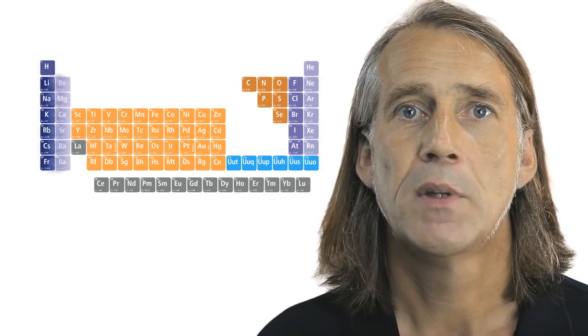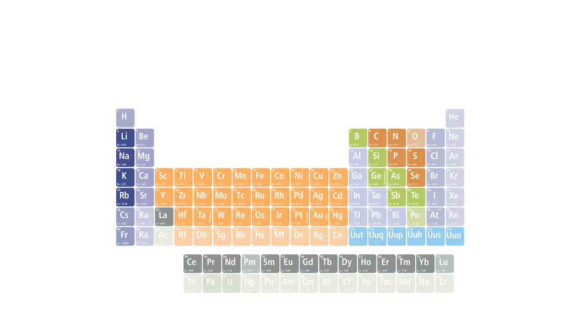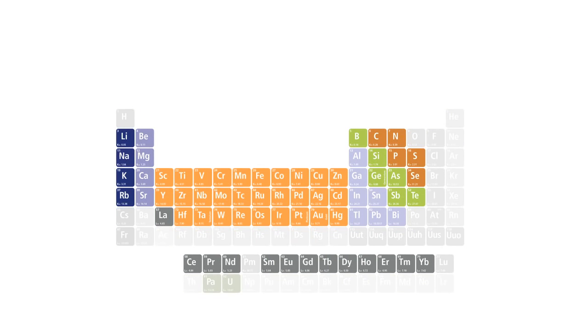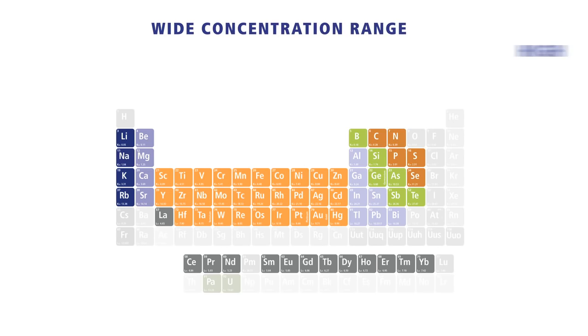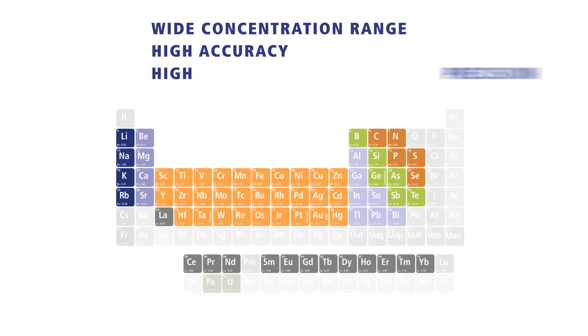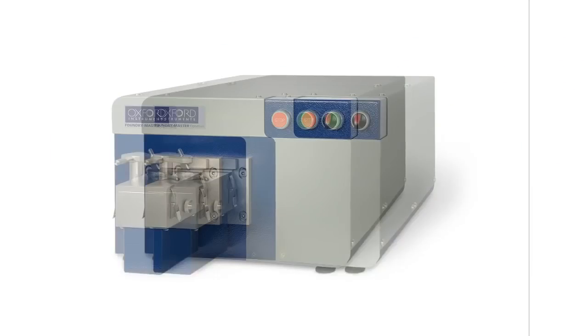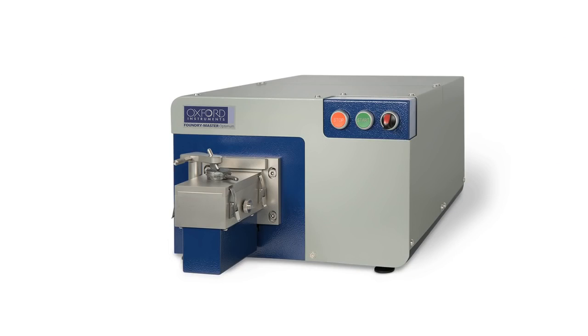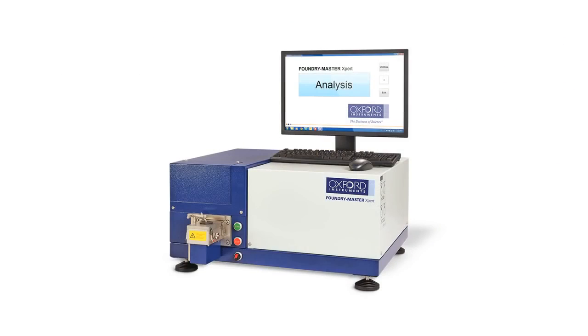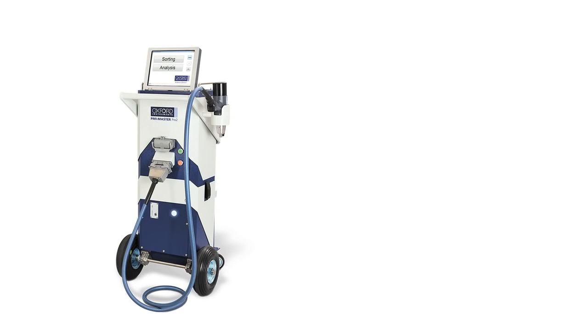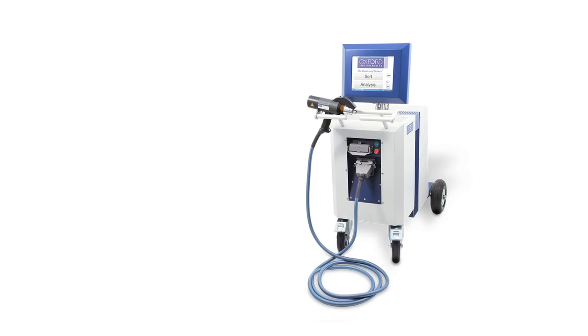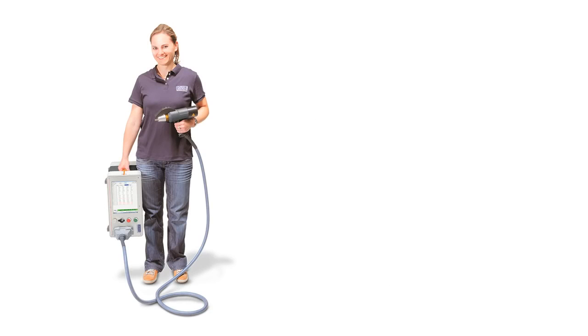OES can analyze a wide range of elements from lithium to uranium in solid metallic samples, covering a wide concentration range and giving very high accuracy, high precision and low detection limits. The elements and concentrations that OES analyzers can determine depend on the material being tested and the type of analyzer used.